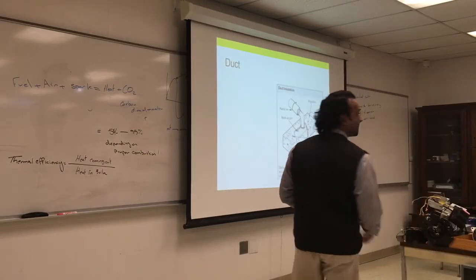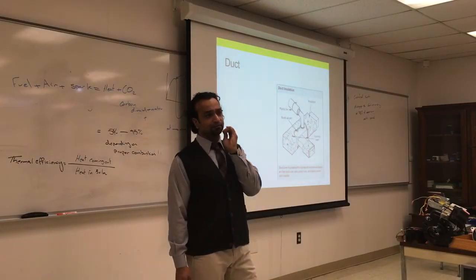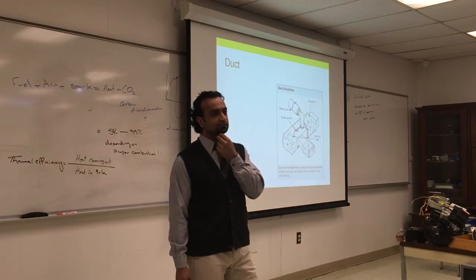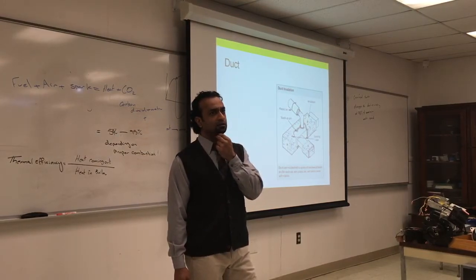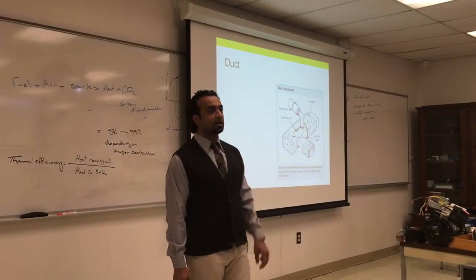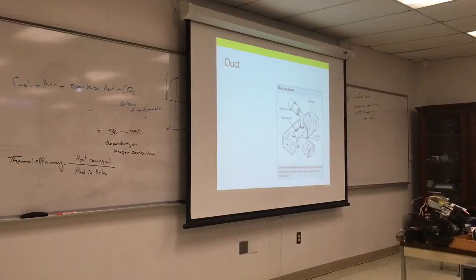There's another thing too: if you cover up any vent, whether it's return or supply, if you cover enough of them up, it could trip a limit switch in the furnace, on high limit or low limit. Probably, yeah. Like with zoning, if you close everything up, you might trip the furnace to shut off because it reached the high limit, yeah.